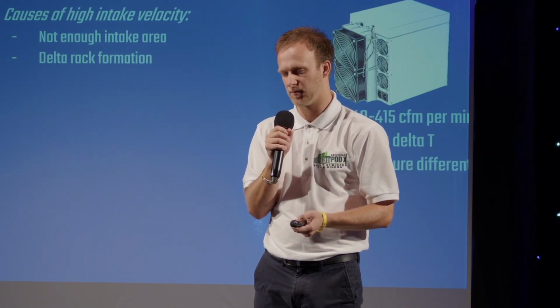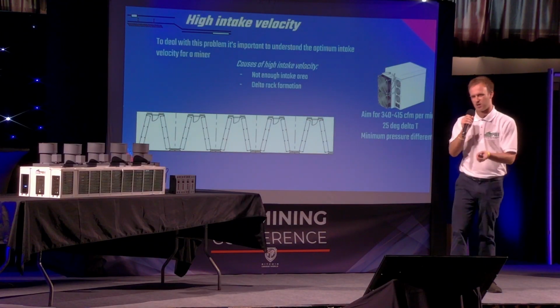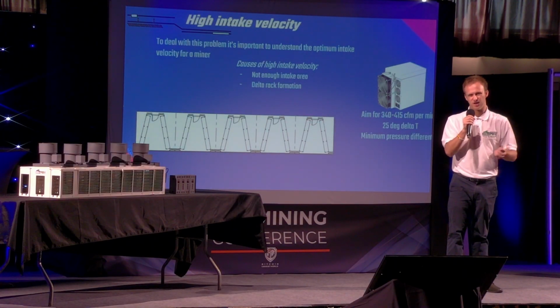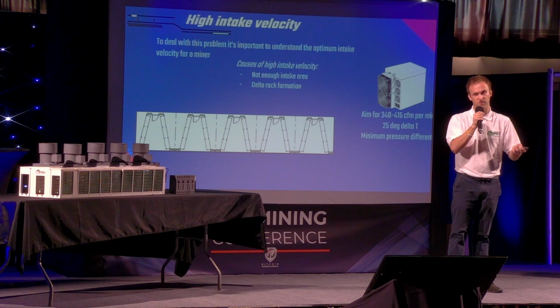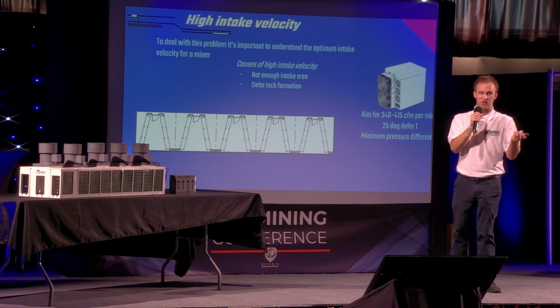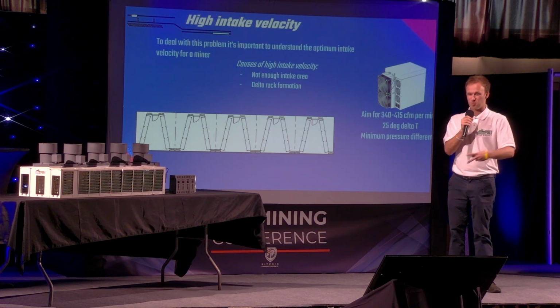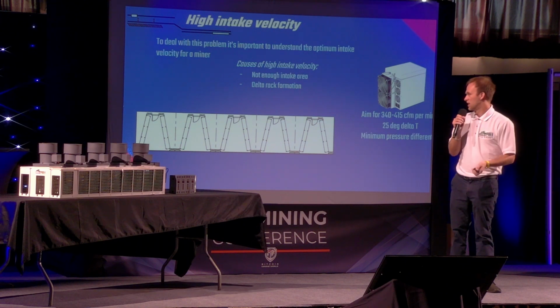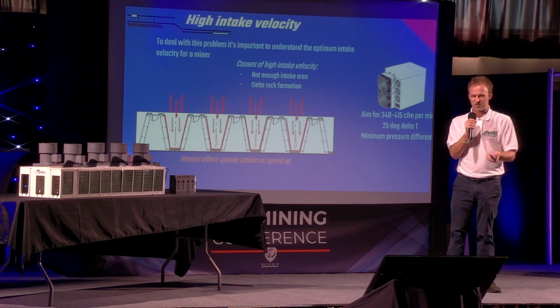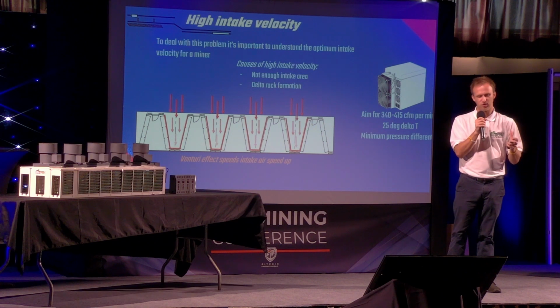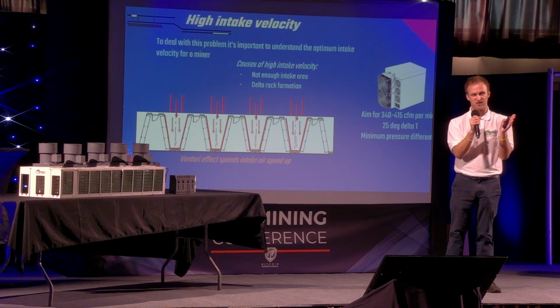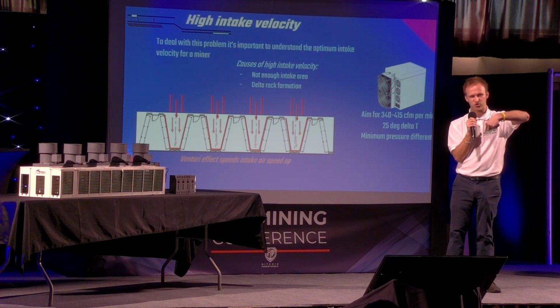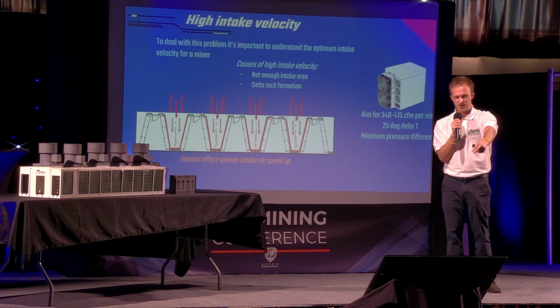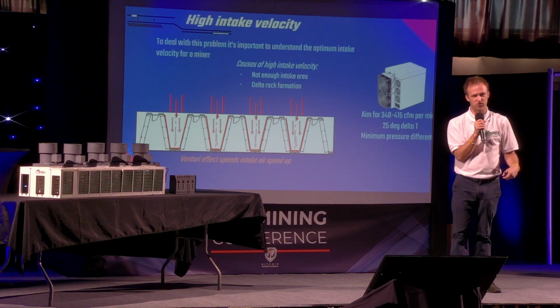And then you also have the delta rack formation. This is an overhead view. You probably understand what this is; you've seen it in other mining pods out there or even buildings. It's a great formation for getting miner density because you can get more miners compared to a streamlined approach, but the problem is you get high intake velocity through each of those deltas. That's because it acts as a kind of Venturi effect, like a vortex funnel, pulling air so fast at the front of the delta that it's actually starving those front rows, those front columns of miners.